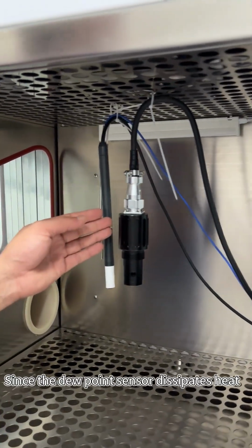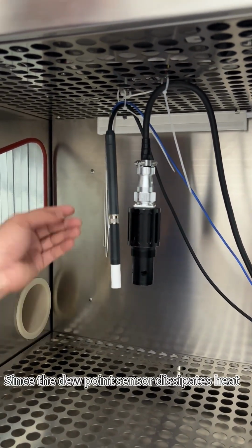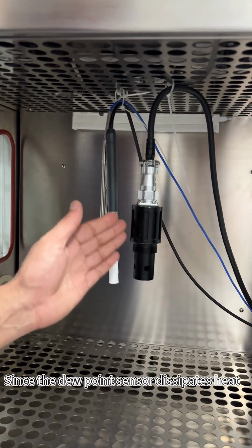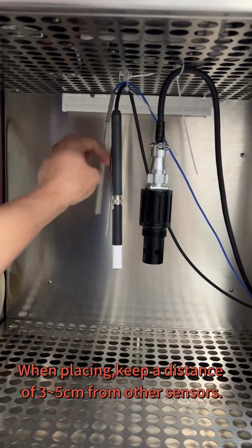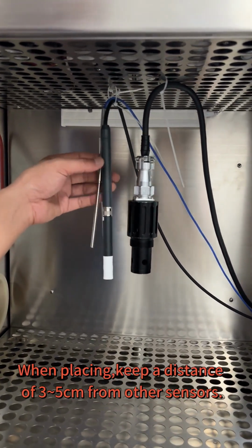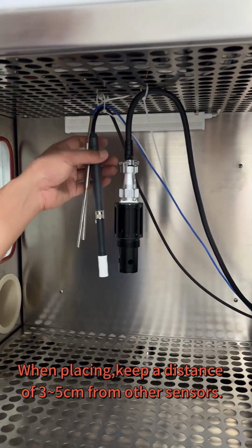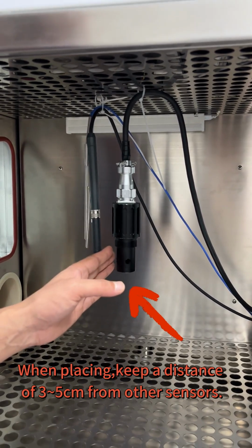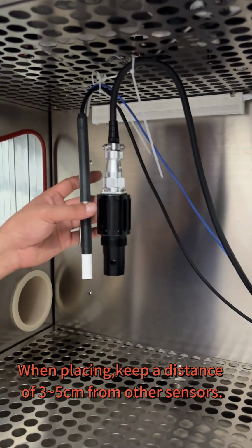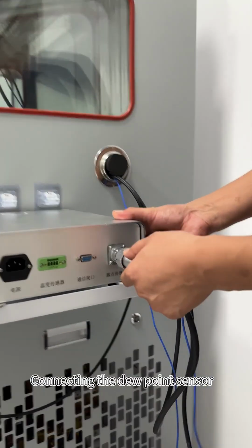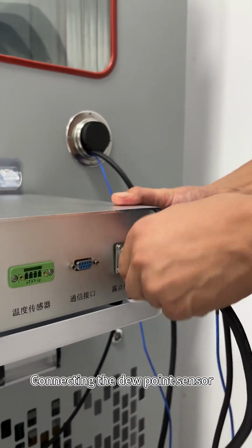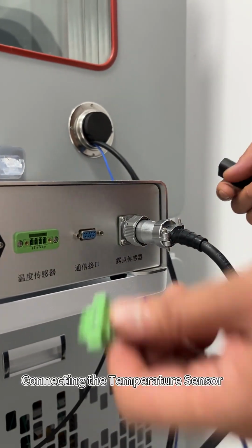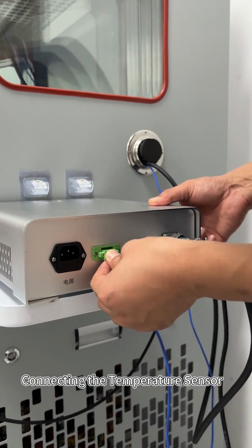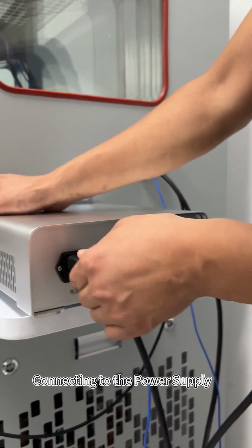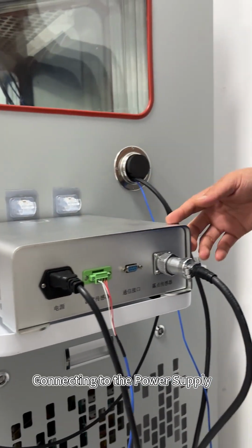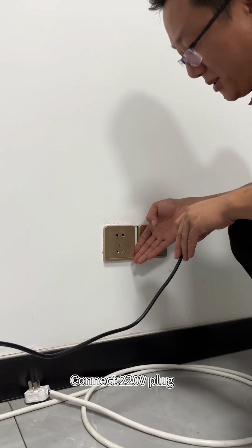Since the dew-point sensor dissipates heat, when placing, keep a distance of 3 to 5 centimeters from other sensors. Connecting the dew-point sensor. Connecting the temperature sensor. Connecting to the power supply. Connect 220V plug.